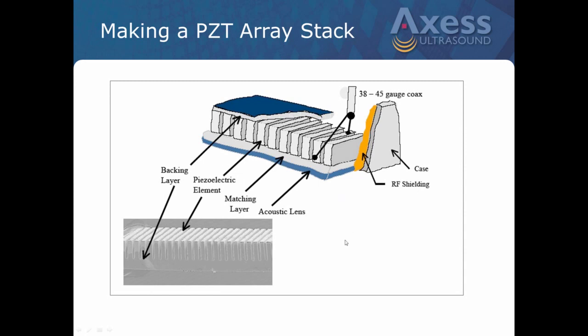So this is kind of from the back side here. Every transducer array has to have a backing layer. The backing layer is used to absorb sound that scatters, so that sound is not passed right through the array and you lose your actual focusing of the beam. Here's your elements through here.